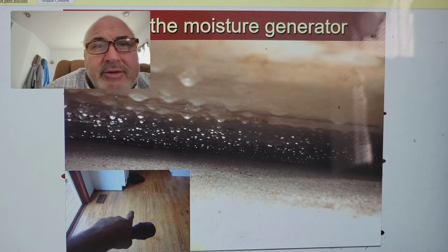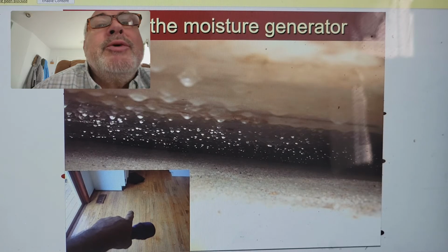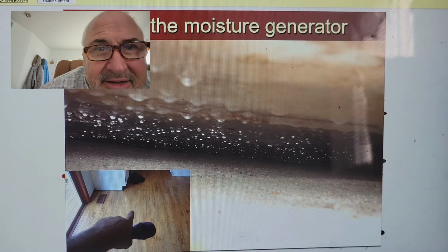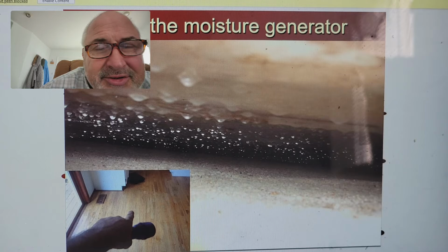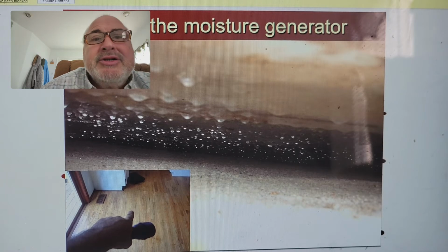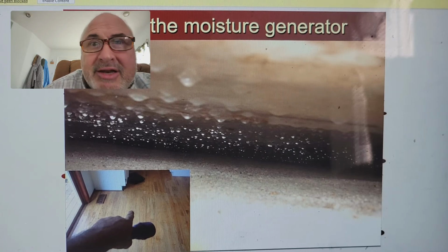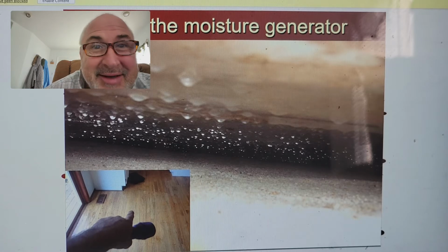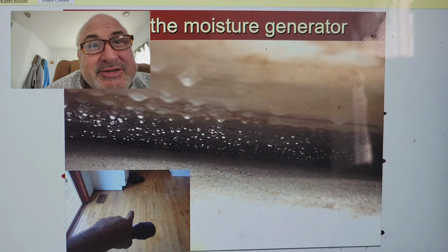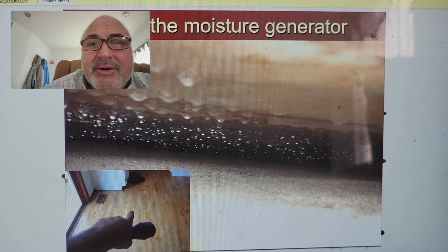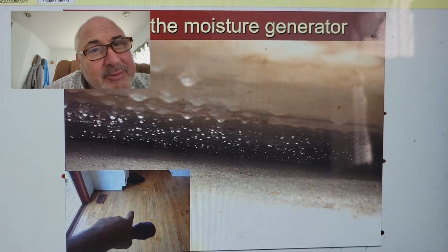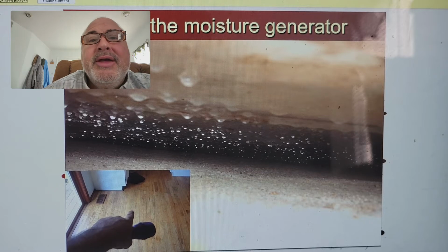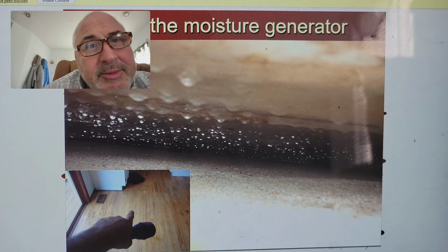And you got humidity, you get formed condensation. So this moisture then starts condensating. It's like an air conditioner condensating underneath your slab. So when the furnace kicks on, you don't even need a humidifier. This is a natural humidifier. And so now you've got mold. Maybe mold could start growing in the attic, or maybe the windows get condensation. This house had window condensation as the issue. And the condensation on the windows was causing them to rot out.